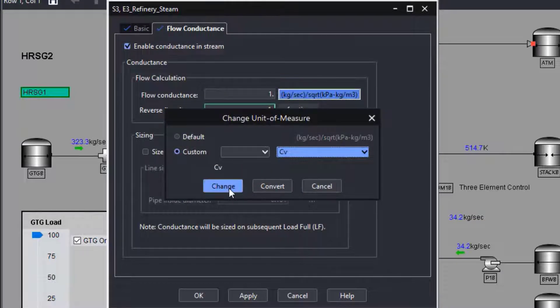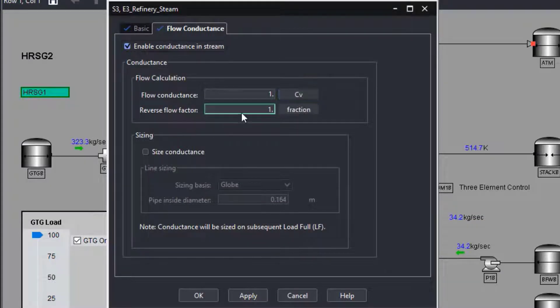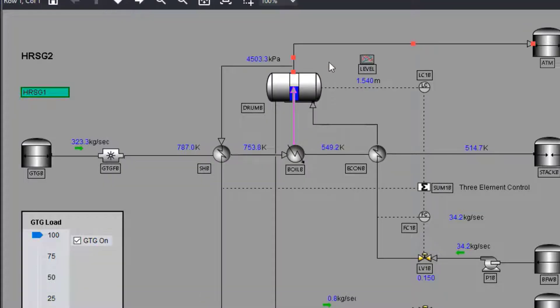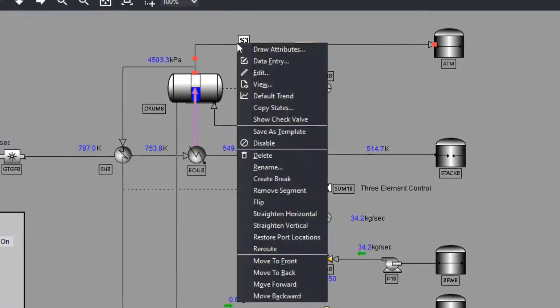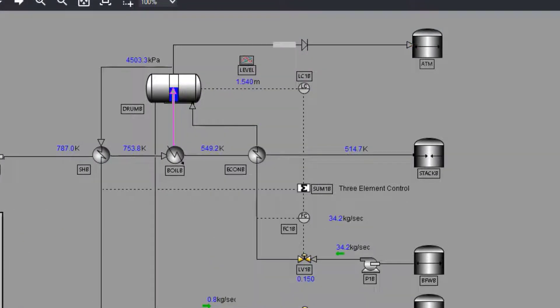simply open the data entry window and enable the conductance. Then enter the desired conductance or use the line sizing to calculate the appropriate value. Use the reverse flow factor to simulate a check valve in the line. A special icon highlights streams with conductance.